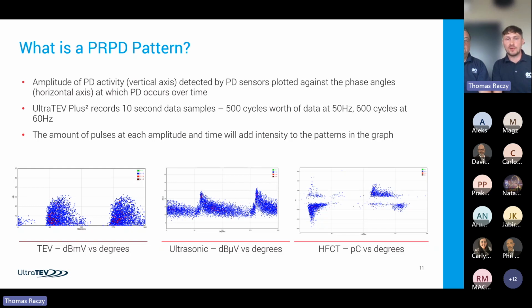So typically when we use the UltraTEV Plus device, when we record data digitally, we typically record 10 seconds of data, which obviously then equates to 500 cycles worth of data at 50 Hertz and 600 cycles worth of data at 60 Hertz.